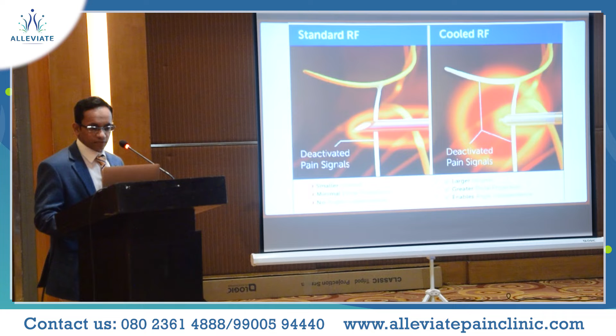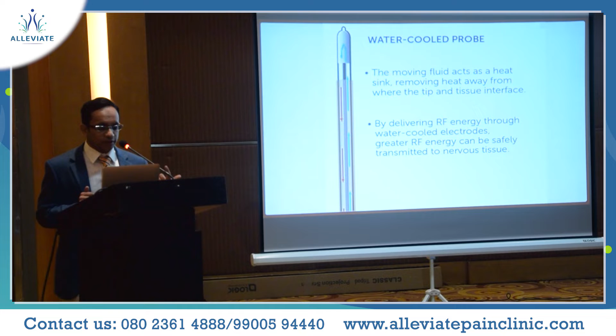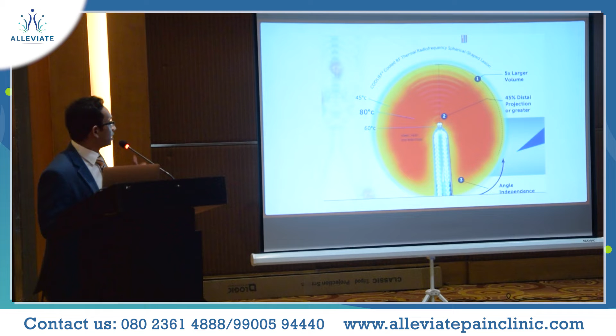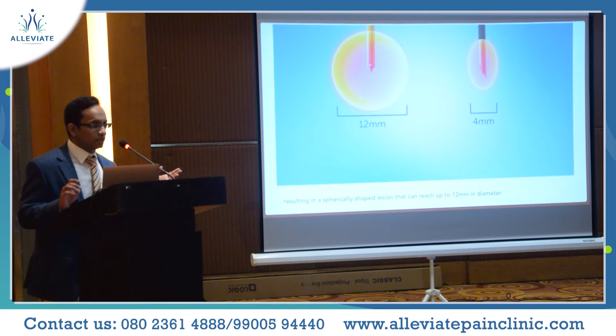So this is the cooled RF probe. It's a water cooled probe. The moving fluid acts as a heat sink, removing heat away from where the tip and tissue interface lies. By delivering RF energy through water cooled electrodes, greater RF energy can safely be transmitted to the nervous tissue. So this is a lesion of the cooled RFA. We can see a 5 times larger volume, 45% distal projection or greater. There is angle independence as well, and you can see the temperatures. This is the comparison between the two lesion sizes. It's about 4 millimeters in a conventional RF, whereas it is substantially larger, a spherical lesion, in the cooled RFA, reaching almost 12 millimeters. Now let's move ahead to the applications.